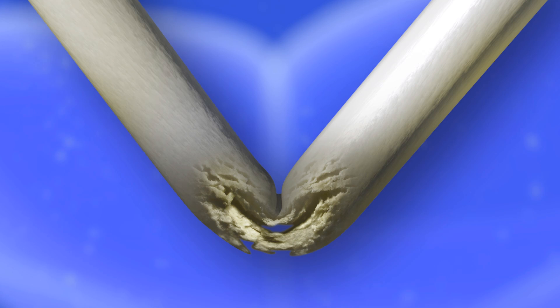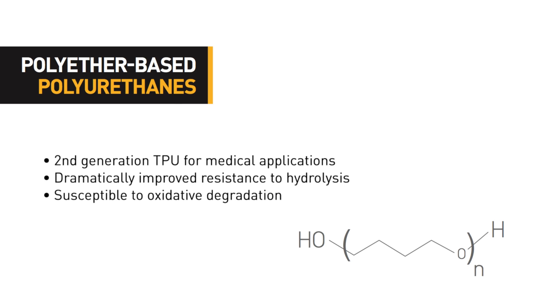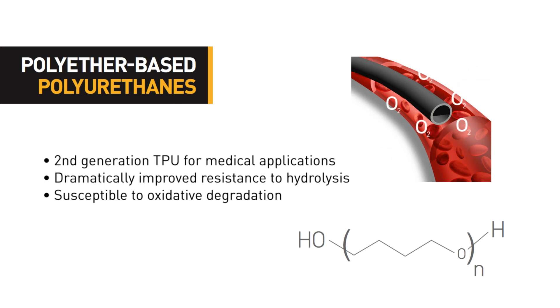In response to the poor aqueous compatibility of polyester-based urethanes, polyether-based urethanes were introduced. Urethanes produced from ether-based chemistry were significantly more resistant to hydrolytic cleavage. But it was found that medical devices were weakened and prematurely failing due to an oxidative mechanism within the body, which degraded the polyether urethanes.